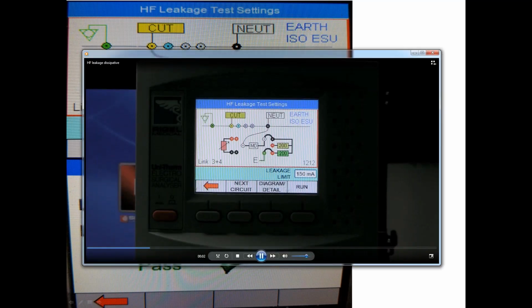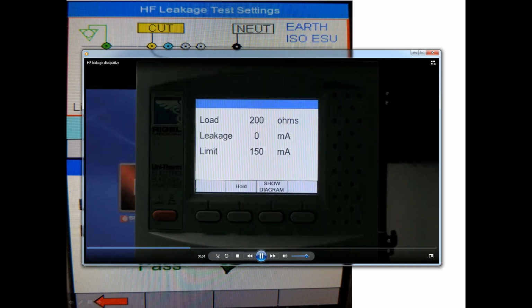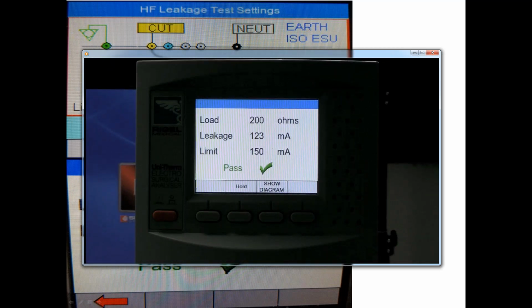Here we're doing the dissipative electrode. And note that it was a bit higher than the active electrode. Pretty common to see, quite frankly. The dissipative electrode quite often is higher than what you would see on the active electrode.